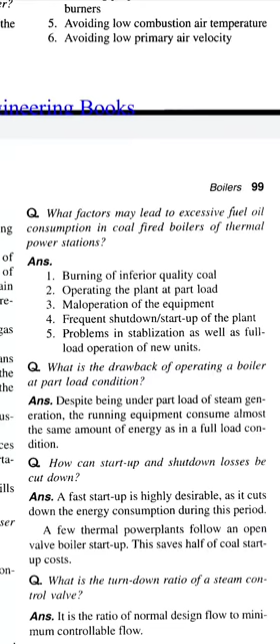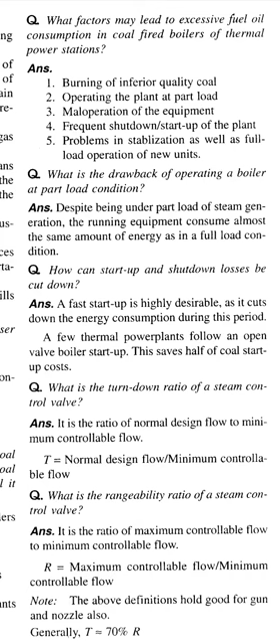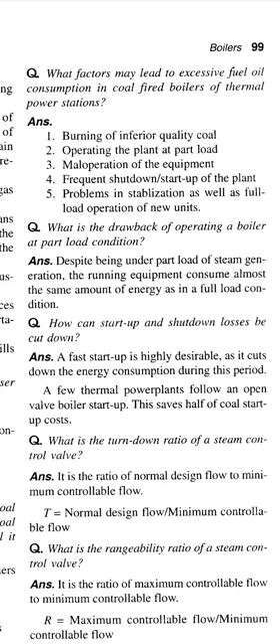And next question. What factors may lead to excess fuel oil consumption in coal-fired boilers of thermal power stations? Answer: burning of inferior quality coal, operating the power plant at part load, maloperation of the equipment, frequent shutdown and startup of the plant, problems in stabilization as well as full load operation of new units. These are the factors that may lead to excess fuel consumption in coal-fired boilers.